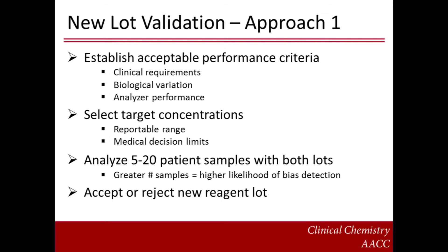Once acceptable performance criteria have been established, the next step is to choose target analyte concentrations. Ideally, the samples should encompass the reportable range of the assay. In practice, however, it may be difficult to obtain patient samples with certain analyte concentrations, and a smaller measuring interval may be taken to represent the consistency of results over the entire reportable range. At a minimum, a laboratory should evaluate samples with concentrations close to the medical decision limits for the test. Once acceptable performance criteria and target analyte concentrations have been chosen, the laboratory can go ahead and test 5 to 20 patient samples with both lots of reagent. The acceptability of the new reagent lot is then decided based on the results of the comparisons. It is important to note that testing a larger number of samples provides a higher likelihood of detecting a problem with the new reagent lot, but test cost and sample availability may sometimes be prohibitive in performing an extensive comparison.